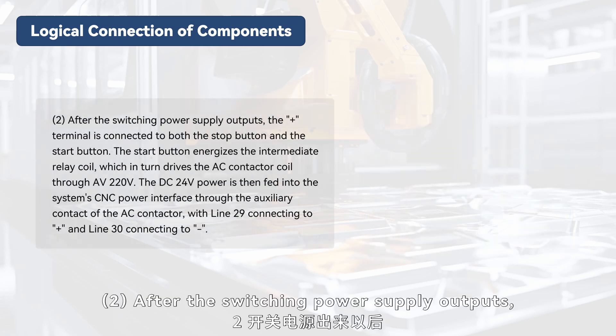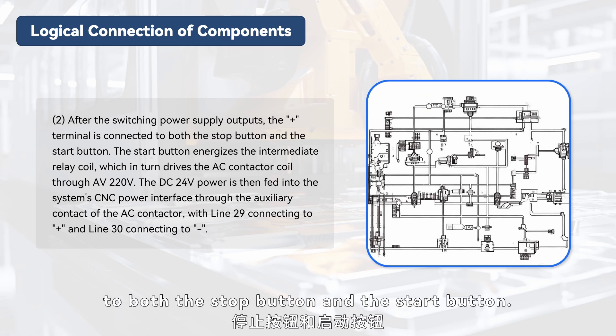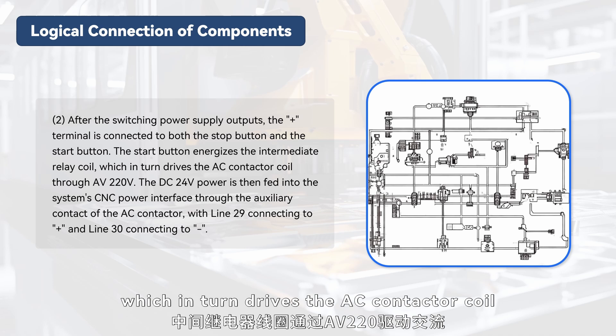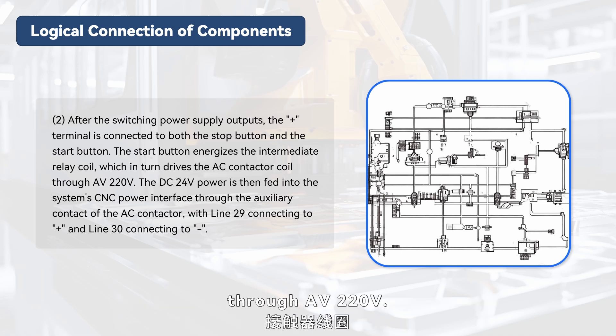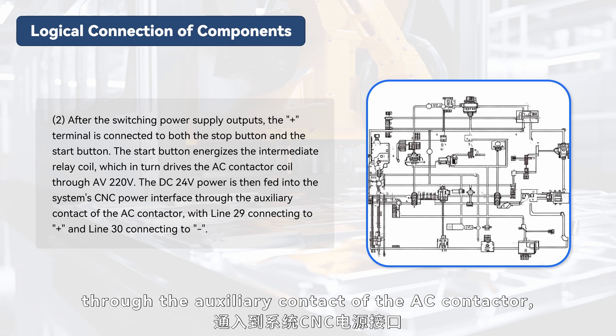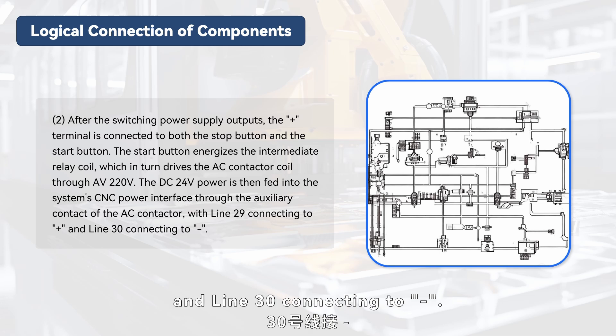Step 2: After the switching power supply outputs, the plus terminal is connected to both the stop button and the start button. The start button energizes the intermediate relay coil, which in turn drives the AC contactor coil through AC 220V. The DC 24V power is then fed into the system's CNC power interface through the auxiliary contact of the AC contactor, with line 29 connecting to plus and line 30 connecting to minus.